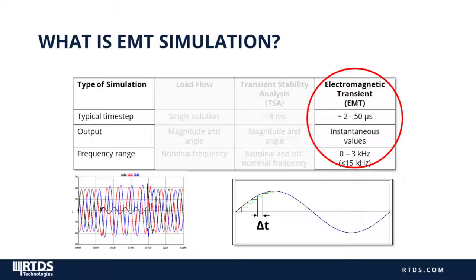The higher the sampling frequency of the simulation, the higher frequency results you can accurately reproduce. The period of the sampling frequency — the distance between two consecutive simulation outputs — is called the time step, or delta t. The typical time step for the RTDS simulator is in the 25 to 50 microsecond range. But if we want to represent high-frequency switching of power electronics, for example simulating converters for interfacing a battery to the grid, we need a smaller time step closer to the 1 to 3 microsecond range.